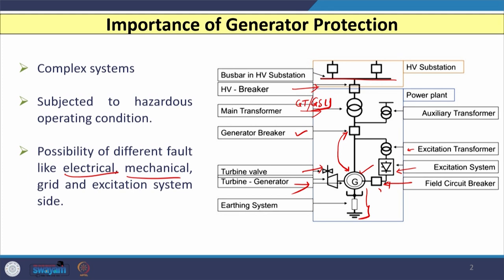Faults are also possible in the excitation system itself. We need to detect the fault if it is in the excitation system and trip the field circuit breaker if required. We also have reverse power — sometimes a situation arises where the synchronous generator becomes a synchronous motor. Instead of delivering power to the system, it takes power from the system, acting as a motor while the turbine or prime mover acts as a load. We need to detect this reverse power flow.